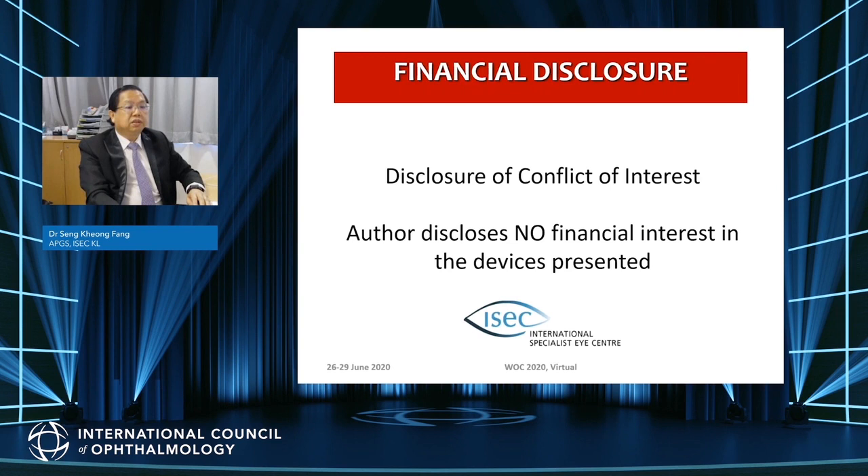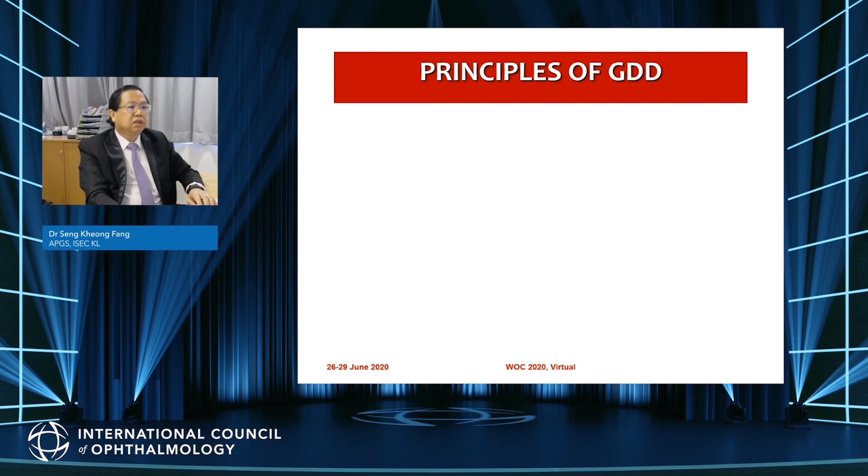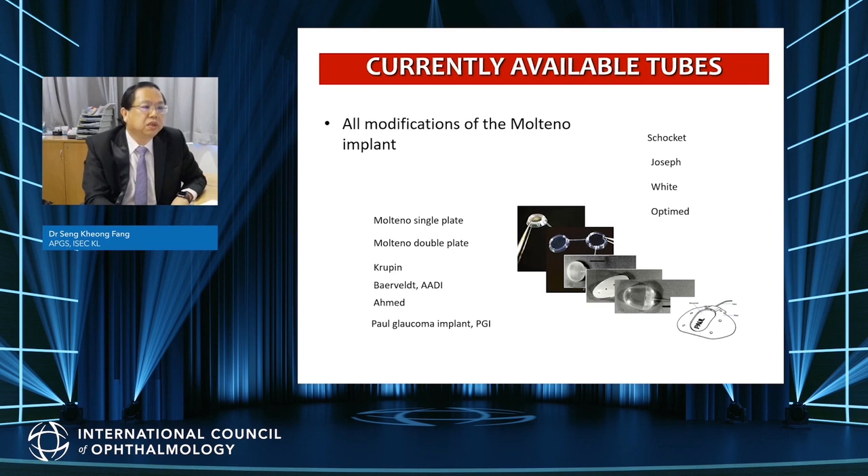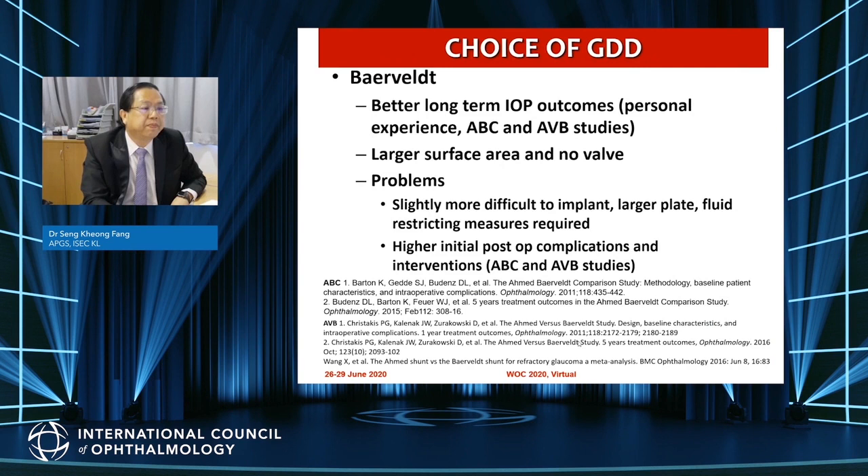I have no financial interest in the devices presented. The principles of glaucoma drainage devices involve creating an alternate aqueous egress pathway by channeling flow from the anterior chamber through a long tube to an equatorial plate inserted under the conjunctiva that promotes bleb formation. There are many tubes available, all modifications of the Molteno implant — familiar ones include the Molteno single and double plate, the Baerveldt, the cheaper Aurolab Aqueous Drainage Implant (AADI), the Ahmed, and most recently the Paul Glaucoma Implant.